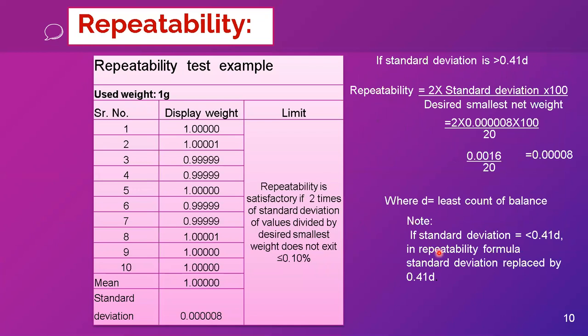To understand repeatability with an example: I took a 1 gram weight and weighed it 10 times, recording each value. I obtained the mean and then the standard deviation. Now, multiply the standard deviation by 2, divide by the smallest desired weight, and multiply by 100. For instance: 0.000008 × 2 × 100 ÷ 20 mg = 0.00008, which is less than 0.10%. So the repeatability test is satisfactory.